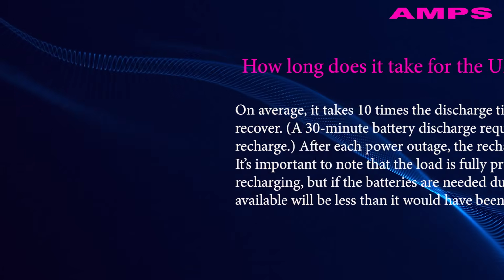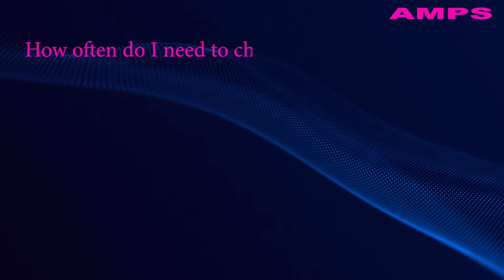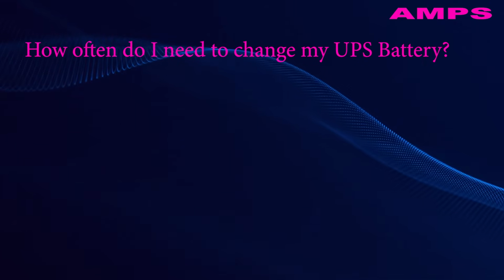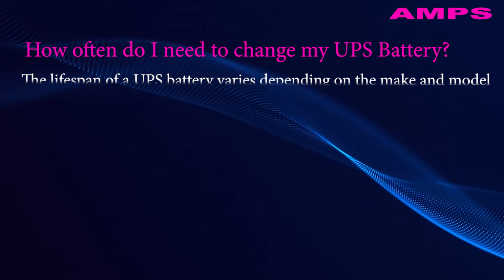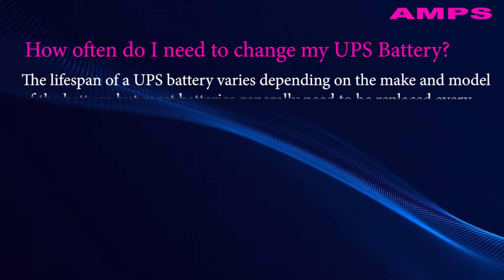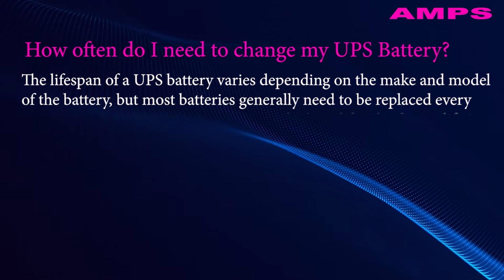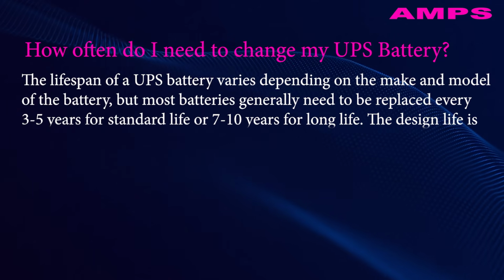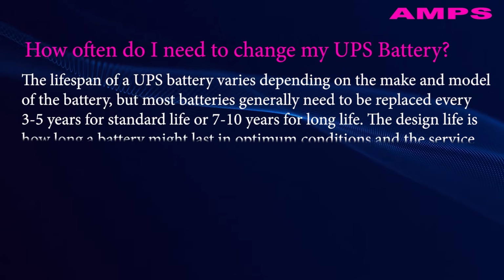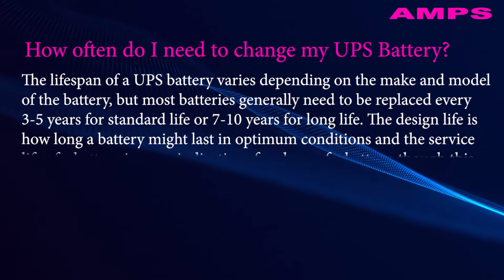How often do I need to change my UPS battery? The lifespan of a UPS battery varies depending on the make and model of the battery, but most batteries generally need to be replaced every 3 to 5 years for standard life or 7 to 10 years for long life.